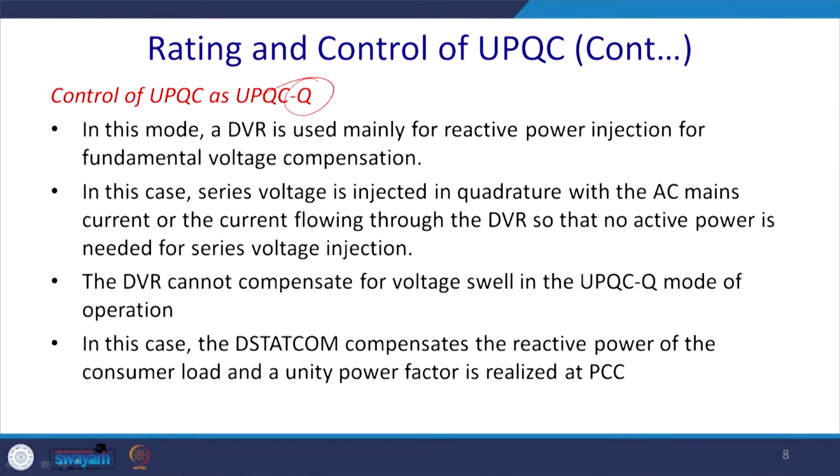We have discussed this UPQC as UPQC-Q. Just a recall, in this mode generally it injects the voltage in quadrature with the current. In this mode the DVR is used for reactive power injection for fundamental voltage compensation. In this case, series voltage is injected in quadrature with the mains current flowing through the DVR, and no active power is required. So its power handling capability is minimum, but effectiveness is also minimum because it only injects power in quadrature.